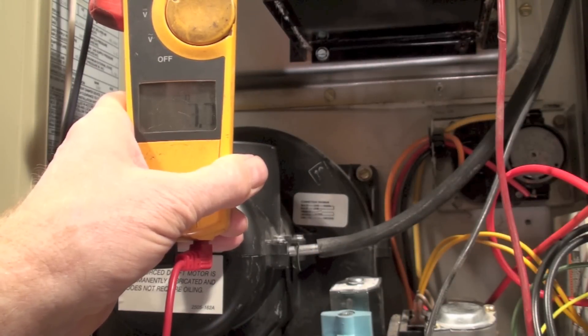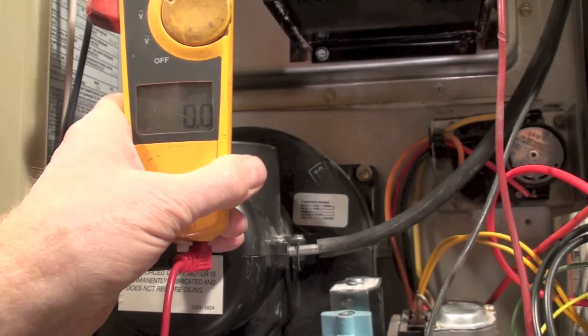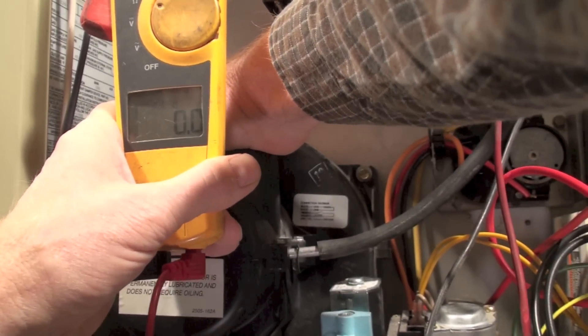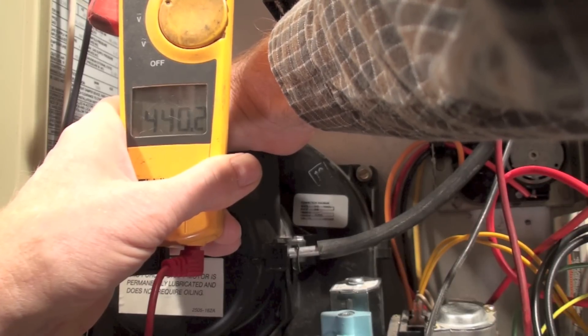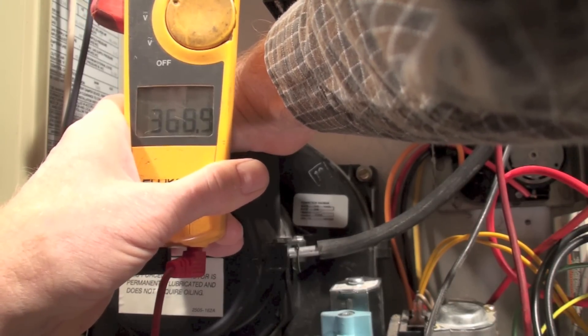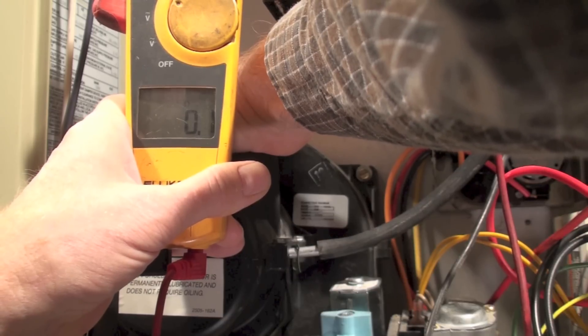And here we are covering up the combustion air inlet, and again you'll see the pressure switch does open when it's completely blocked off.